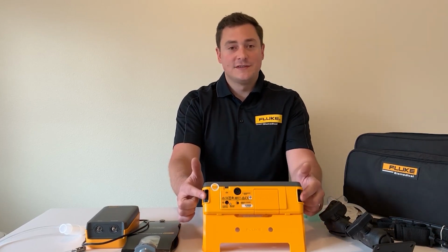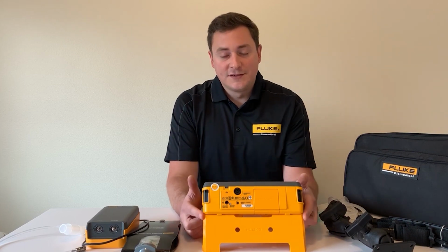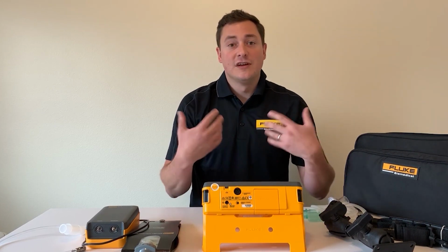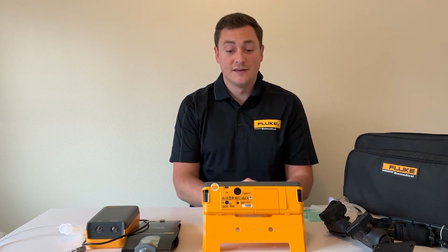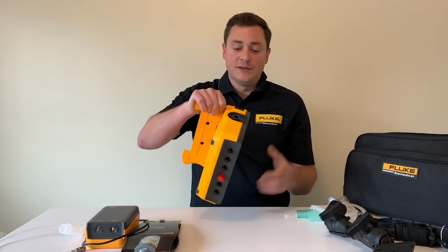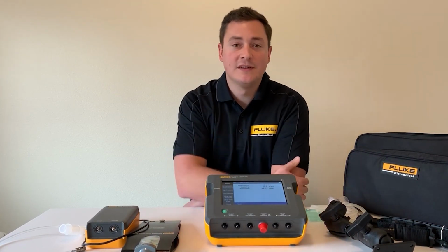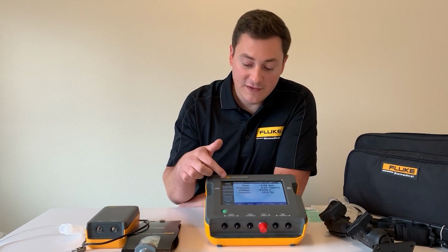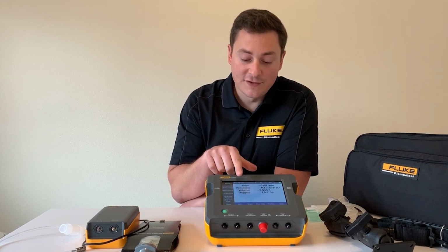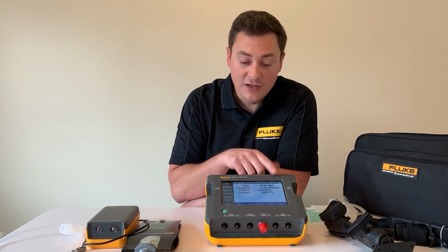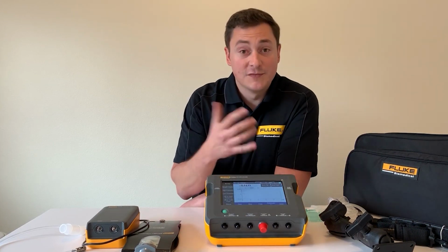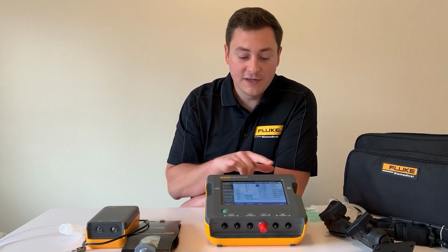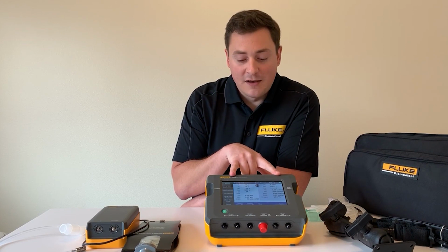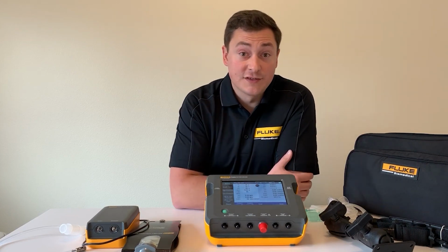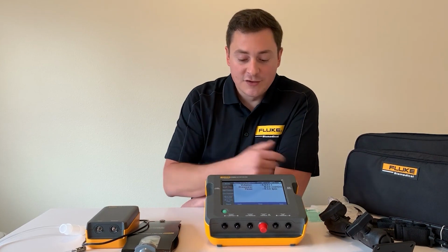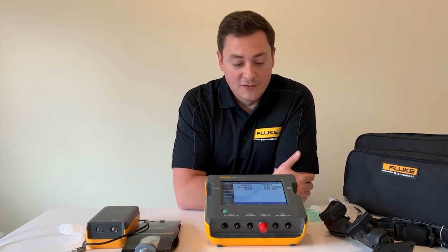Some integrating handle options that I'm going to touch on a little bit later, and a tilt-up bail here that puts your unit at a 45-degree angle so that you're able to read it as you put it on a tabletop. The one thing that you'd probably notice first was the 7-inch color touchscreen display. So here on the airway screen, you can see that flow, pressure, volume, and oxygen are all displayed numerically. You also have the flexibility to show that graphically, so that's something that's really nice to have. On the breath view screen, you can show all 16 breath parameters, or if your procedure doesn't call for that, I went ahead and customized view 1 to show only volume, pressure, and flow, and that made those readouts larger.